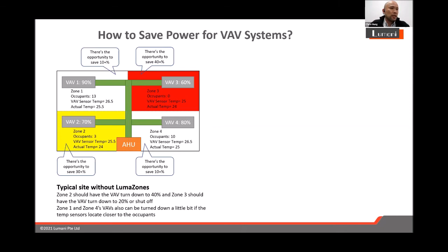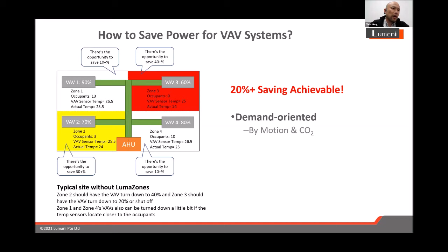We just use a demand-oriented algorithm by the motion and CO2 level to decide if the zone is occupied. Then we use a remote sensor to calibrate the correct temperature setting. Usually the VAV's temperature sensor is in the air intake, and it's usually hotter, 1 or 2 degrees higher than the temperature with the occupants. So it's actually a waste. If the sensor reaches the set point, it will be too cold for the occupants. So we can use a remote sensor to calibrate the temperature, and you can save at least 10% there.